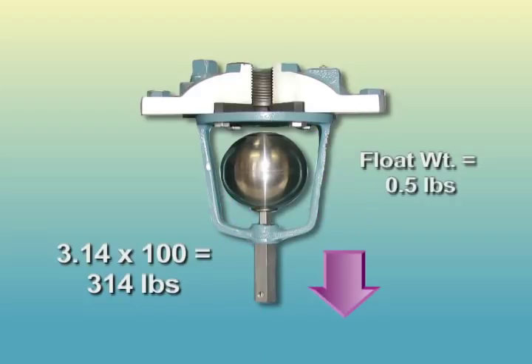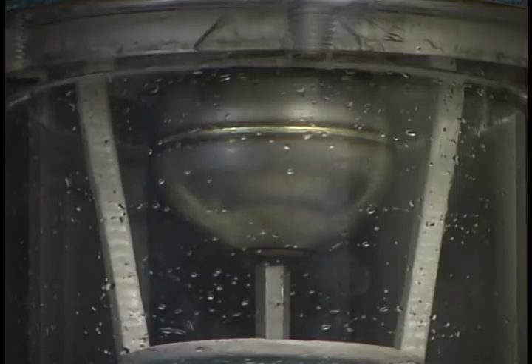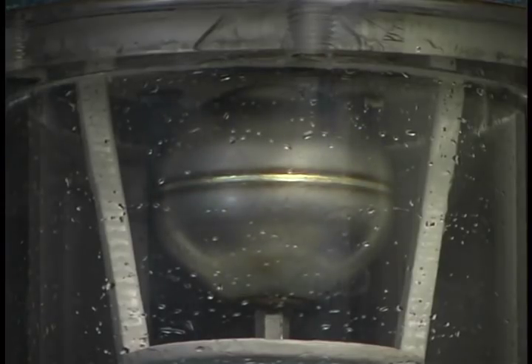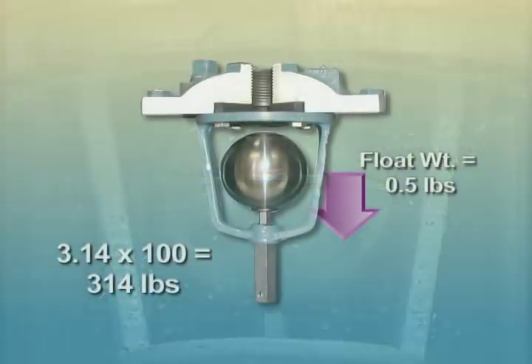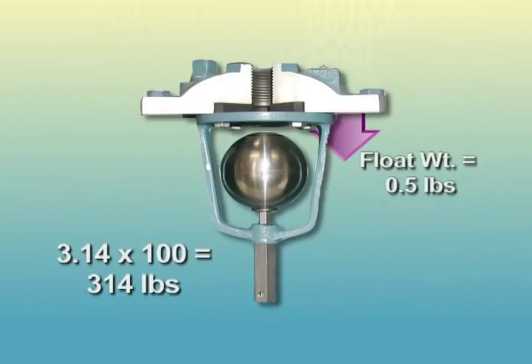An important benefit of an air vacuum valve is its ability to provide pipeline vacuum protection. If a system failure or column separation occurs and a negative pressure develops, the valve will open, admitting air into the line and preventing vacuum conditions, which can lead to a possible pipeline collapse or intensified air-related surge. While air vacuum valves will exhaust large quantities of air upon startup, it should be remembered that they will not continuously release air during system operation.